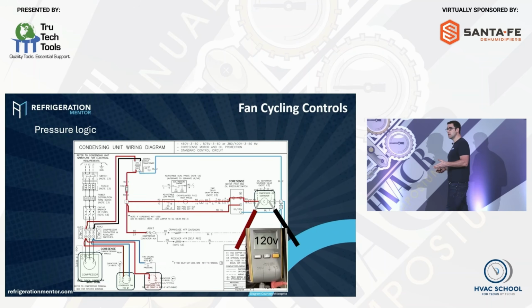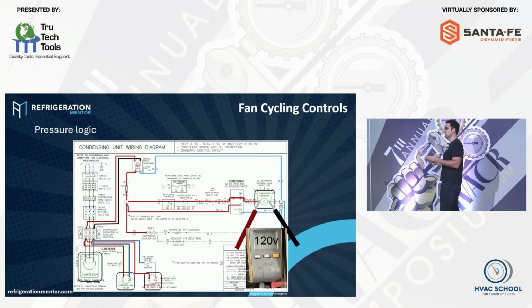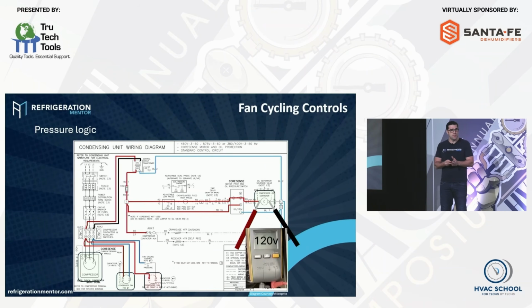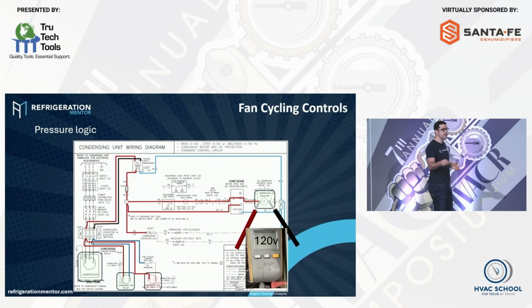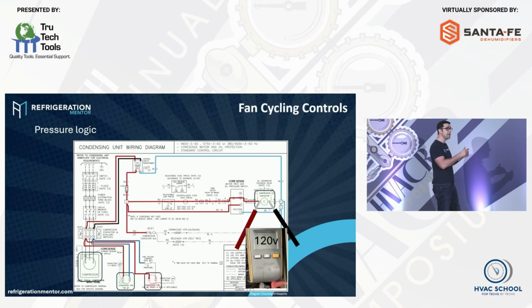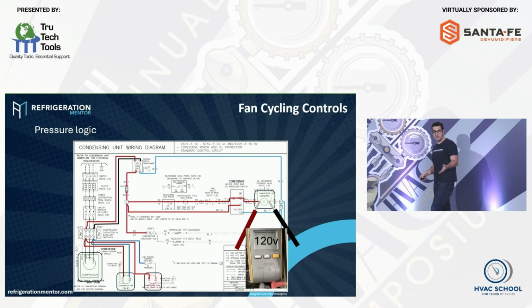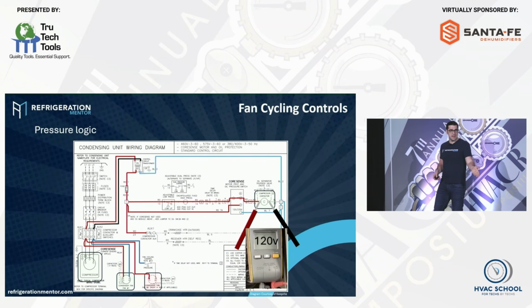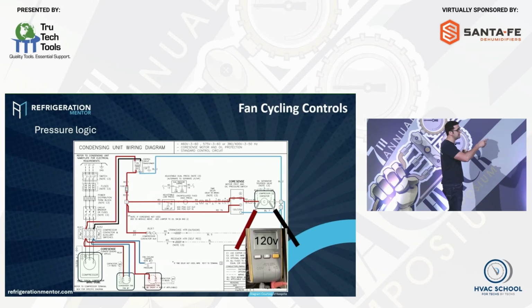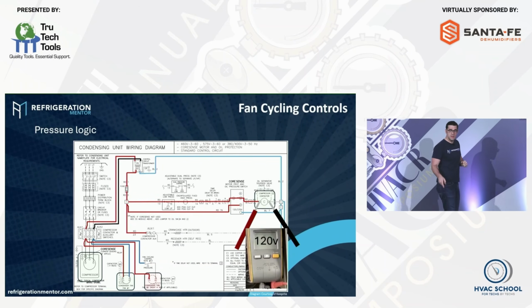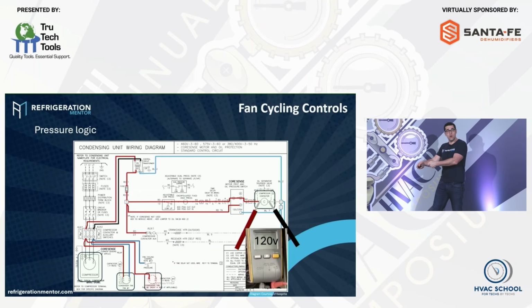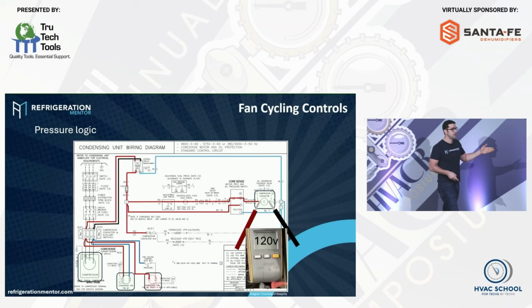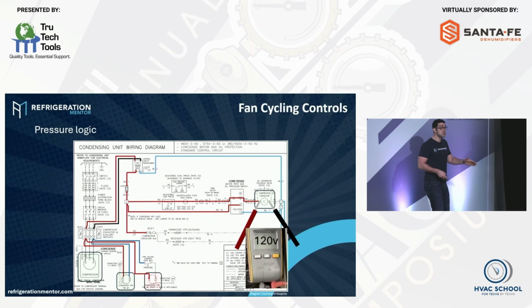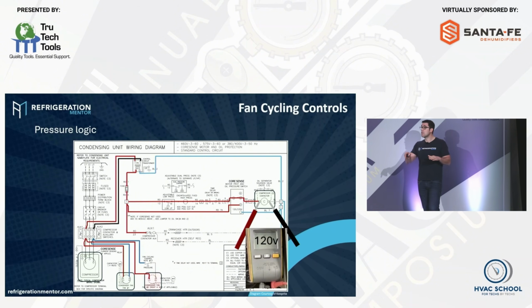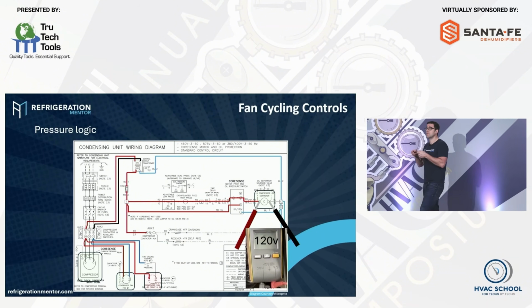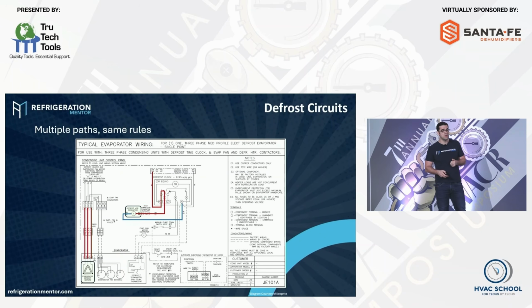Then when we get to fan cycling control, there's pressure logic. Well, what does pressure logic mean? As the pressure goes into some sort of component, a low pressure control, high pressure control, a fan cycling control, it will change the contacts depending on that setting. For this example here, that condenser 2 fan is not running, and you can't see it. In the documents at the end, you can get these presentations for free and just look at them. But the condenser fan's not working right now. We got power to the coil, but it's not working because there's a fan cycling control there. Now, if all of a sudden your pressures get really high and that fan is still not running, then we would have to go and check to see if that pressure switch is working or not. And that's how we would use our meter.